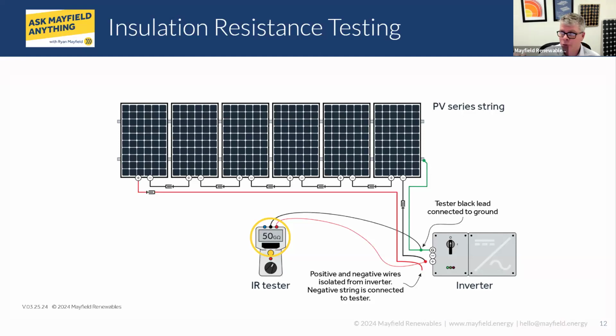A comment came through from Richard. Richard, I really appreciate that. Thank you for this. It's probably one of the biggest things we should highlight if we're not going to be able to go through every single part of doing this test: the voltage ratings of your module. Richard's comment was, if the modules are rated for 1,000 volts but the conductors are rated for 2,000 volts, 1,500 volt tests should not be performed due to potentially damaging the module. And 100% you are correct.